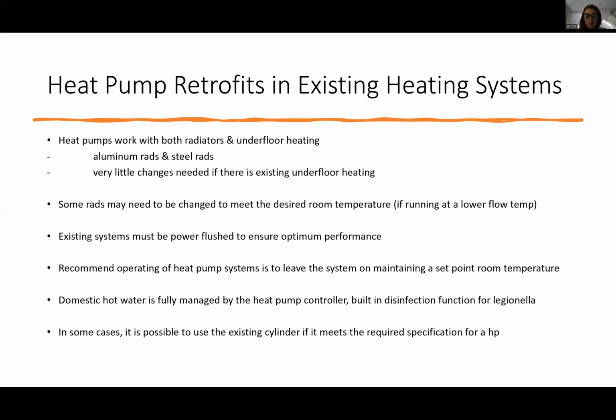And in some cases, in retrofit, I suppose over the years, people, when they were building a new house, were considering future-proofing at the time, even if they didn't put in a heat pump initially. A lot of the time, people did put in a cylinder that would be suitable if they put in a heat pump down the line. So sometimes the cylinders can be used. There is a specific requirement for the coil size of the heat pump. It needs to be larger than what it would be to be heated from an oil or a gas boiler. So that just needs to be checked. But in cases where you can use the existing cylinder, it reduces the disruption in the house in terms of rerouting pipework or changing pipework. So while it is daunting, the thoughts of having to retrofit all of these heat pumps, it is doable, and we will get there, but with a lot of hard work, I think.